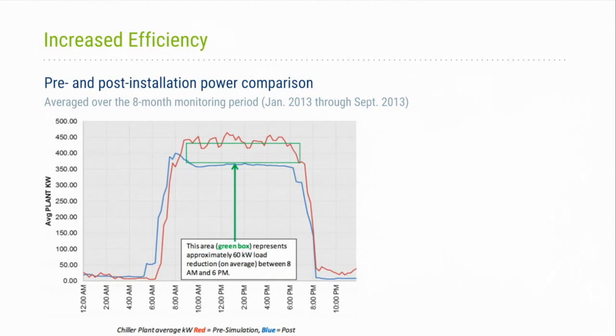Part of the measurement and verification that occurred by the National Lab over an eight-month period from January 2013 through September of 2013 was based on how the system was designed with the variable speed pumping operations and the variable speed tower fan operations. As you can see in the graph, the green box represents on average the savings that was identified through that monitoring period. Some things are important to note: the red line represents the average kW based on a simulation period. We had no baseline data for this site, so coming up with a baseline was a little bit challenging.